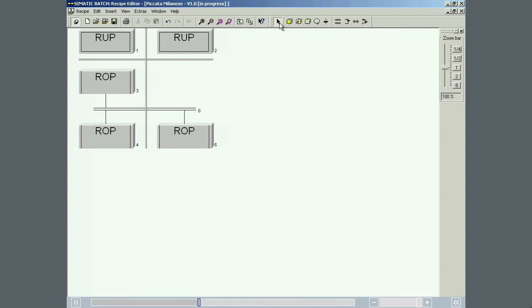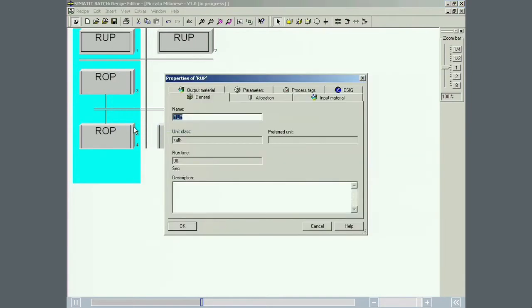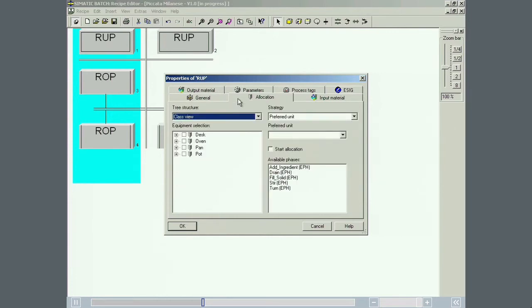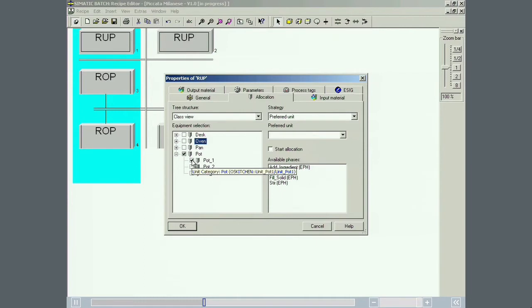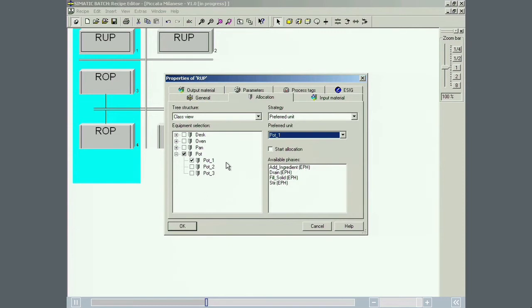A previously created recipe structure will be used as the basis for our piccata milanese product. The left-hand recipe unit procedure is assigned a unit using the preferred unit allocation strategy. The pot 1 unit is assigned to this recipe unit procedure. This is the point at which the integration of Simatic Batch becomes obvious. All the units and the available equipment phases defined in the engineering system are available in Simatic Batch for creating master recipes without any additional engineering effort.